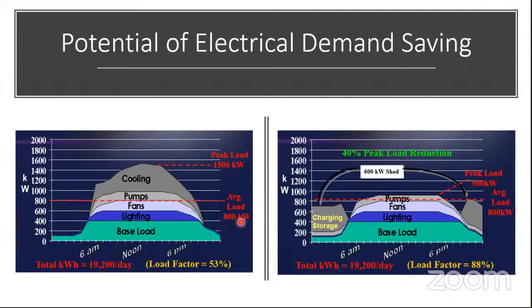These figures are just to take an example. However, what is to be seen here is that despite the average load being 800 kilowatt, one has to install a 1500 kilowatt chiller plant. So the load factor here, which is the average load versus peak load, is actually very poor.